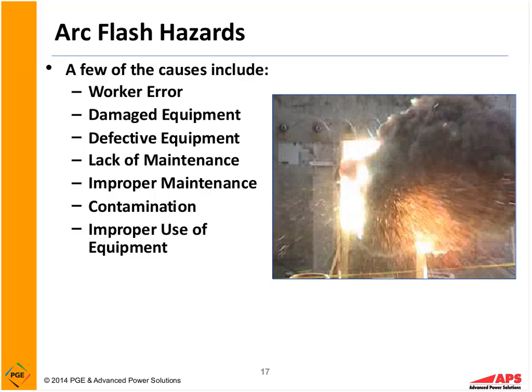Okay. Damaged equipment. I've had several cases of damaged equipment. Defective equipment. I've had equipment come right out from the factory that's been defective and created an arc flash. Lack of maintenance is another big one here, not maintaining our equipment properly, or improper maintenance. Contamination. Sometimes I work in high-tech firms where they have semiconductive dust that gets brought into the equipment through the vents or through the fans. Inhaling that for cooling air brings in semiconductive dust, which will conduct at some point in time. Okay? Improper use of equipment. And also we have improper installations as well.